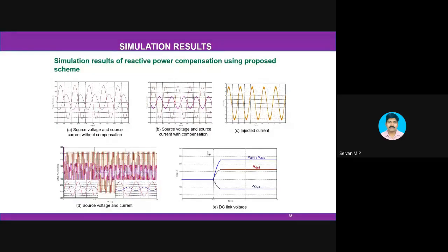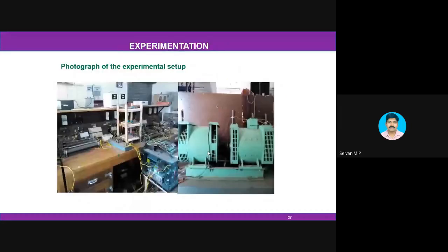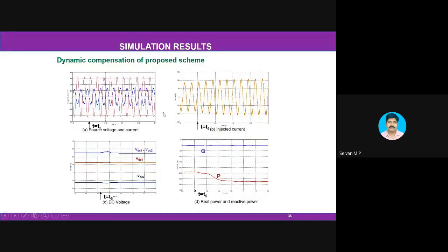So see here, this is a normal operation. This is the voltage source and current, and this is the injected current by the STATCOM. What is important to see is this power graph. Real power is negative, which indicates that power is going from the machine into the grid. Reactive power drawn from the grid is assumed to be positive. So here you can see that reactive power drawn from the grid is zero because the STATCOM is supplying. Even though there is a variation in power, the STATCOM is able to supply the required reactive power and it maintains unity power factor at the connection point.